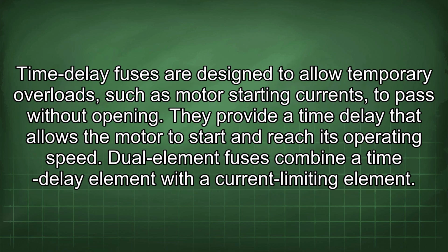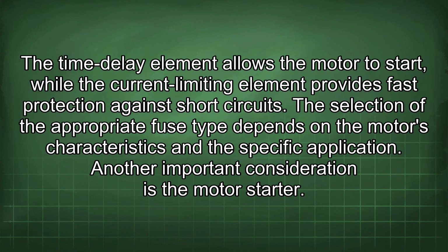Time delay fuses are designed to allow temporary overloads, such as motor starting currents, to pass without opening. They provide a time delay that allows the motor to start and reach its operating speed. Dual element fuses combine a time delay element with a current limiting element. The time delay element allows the motor to start, while the current limiting element provides fast protection against short circuits. The selection of the appropriate fuse type depends on the motor's characteristics and the specific application.